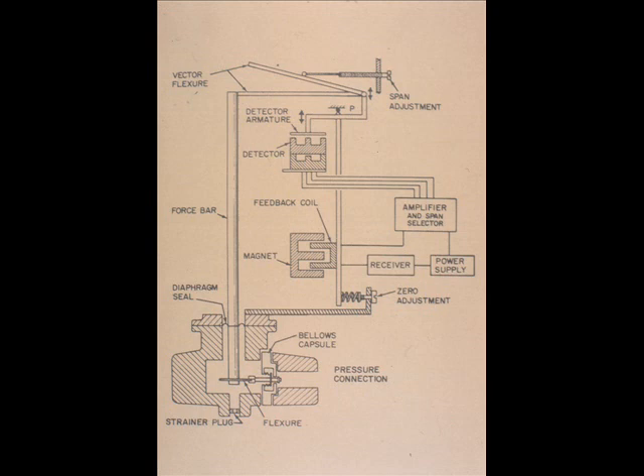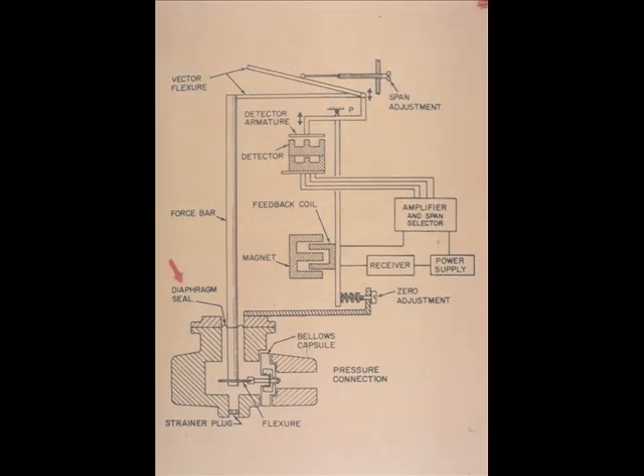This is a component diagram of the E11GM. It is a force balance transmitter and will convert gauge pressure to 10 to 50 or 4 to 20 milliamps DC. Locate the diaphragm seal. Above this seal, the schematic is identical to the E13 for differential pressure.